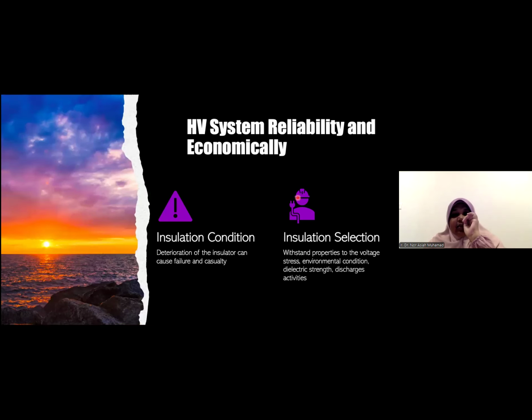So now for the high voltage system, reliability and economics depend on the insulation condition and insulation selection. That's why in high voltage monitoring, we are monitoring the insulation condition. Deterioration of the insulation can cause failure and casualty. So for insulation material, we do testing to know the condition of the equipment and also to detect or predict faults inside the equipment.